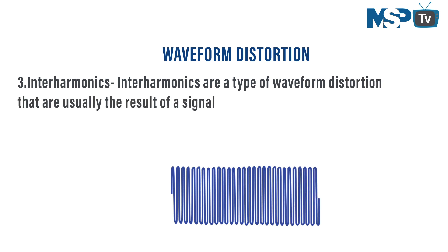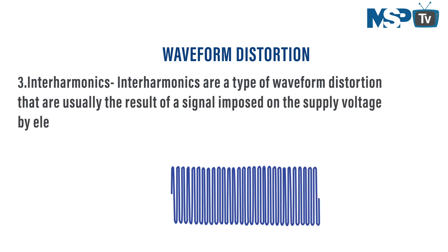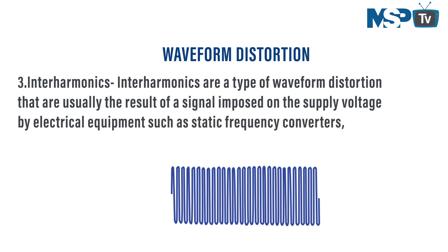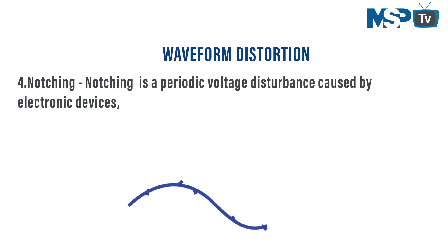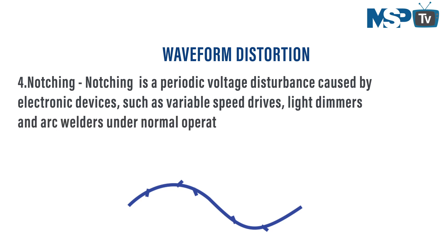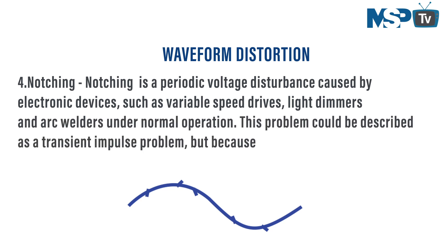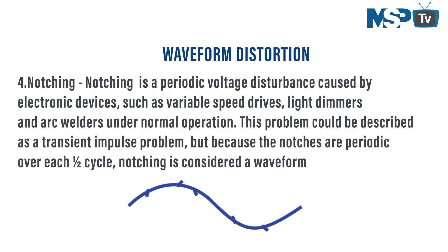Third, interharmonics: interharmonics are a type of waveform distortion usually resulting from a signal imposed on the supply voltage by electrical equipment such as static frequency converters, induction motors, and arcing devices. Fourth, notching: notching is a periodic voltage disturbance caused by electronic devices such as variable speed drives, light dimmers, and arc welders. Under normal operation this may resemble a transient impulse, but because the notches are periodic over a half cycle, notching is considered a waveform distortion problem.